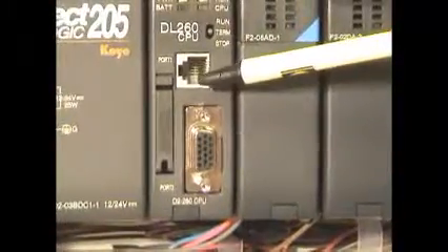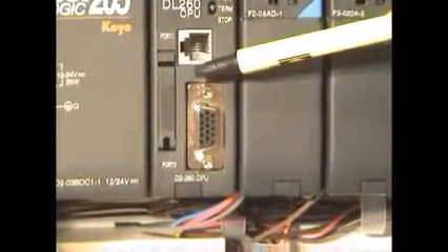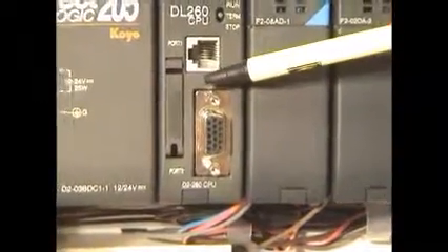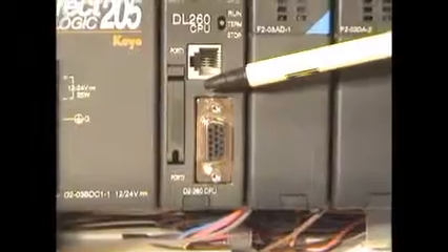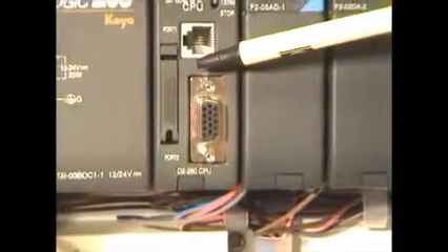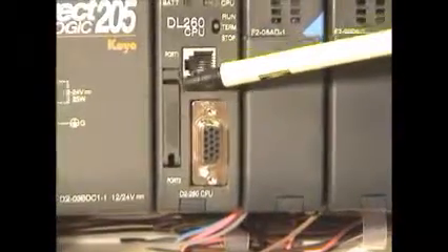Inside the CPU module there's also a battery to back up the data. This battery should be replaced every 2 years. To replace the battery, simply push down on the tab and gently pull the battery holder out and pry the battery out of the holder.